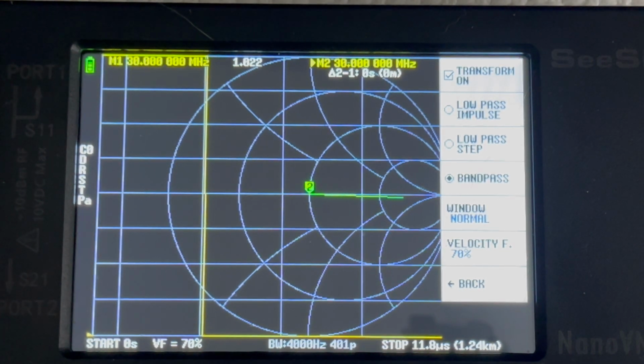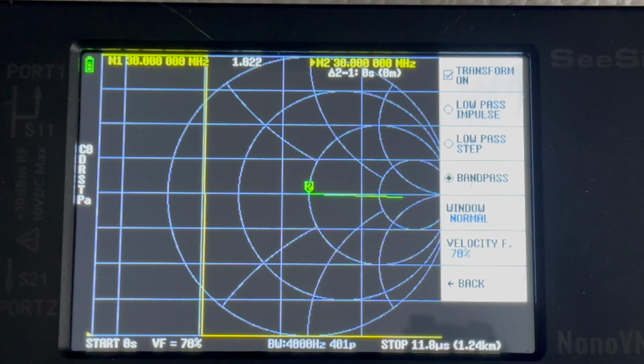And apparently, for accuracy, the first thing you gotta do is set the start frequency to, I believe it's 50 kilohertz. I'll have to look that up. I believe that's what it is. And then the stop. The shorter the measurement frequency, the longer the maximum time length. So let me understand this. A lower frequency to measure longer length and a higher frequency to measure a shorter length. So selecting frequency for testing is essential. I probably would have set this around 10 or 20 megahertz, because I'm only talking about, in this case, about 100 feet of cable.